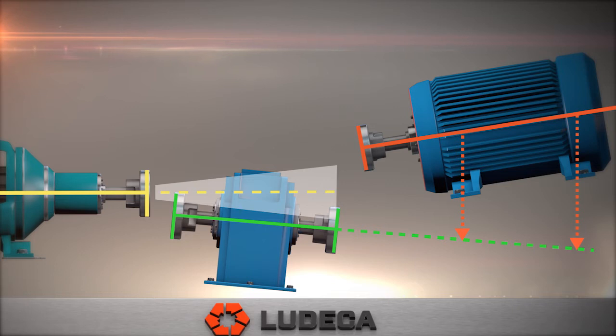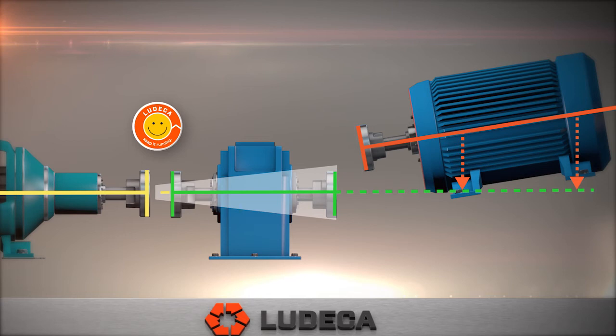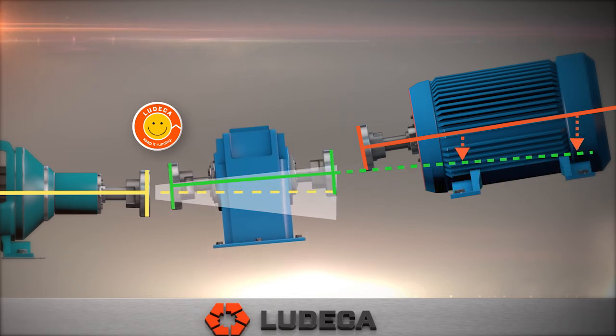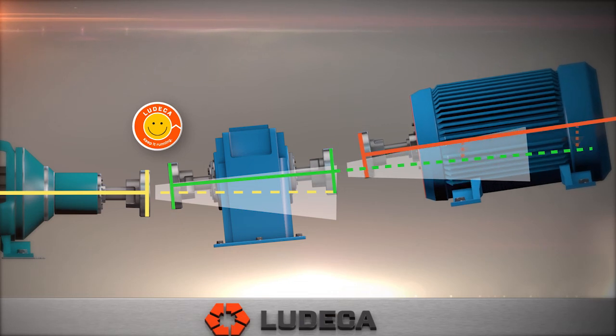Doing a perfect alignment to the pump may not solve your problem. In this case, the goal is to move the machines so that they are all aligned within tolerance. So we take advantage of the full value of our tolerance envelope to move the gearbox to where the motor can now be aligned to it.